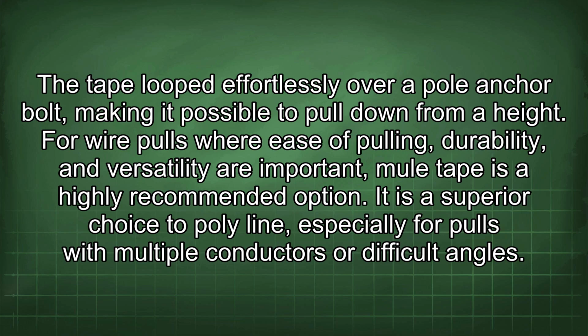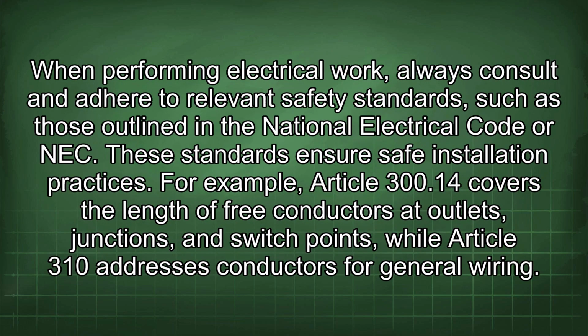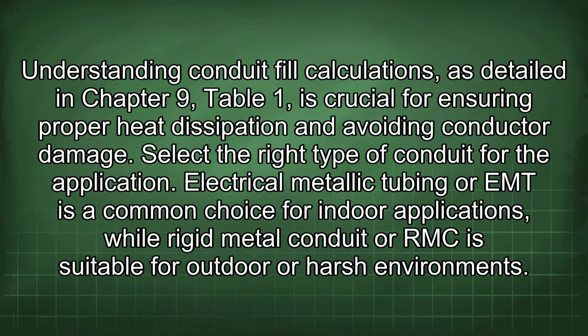For wire pulls where ease of pulling, durability, and versatility are important, Mule tape is a highly recommended option. It is a superior choice to polyline, especially for pulls with multiple conductors or difficult angles. When performing electrical work, always consult and adhere to relevant safety standards such as those outlined in the National Electrical Code, or NEC. These standards ensure safe installation practices. For example, Article 300.14 covers the length of free conductors at outlets, junctions, and switch points, while Article 310 addresses conductors for general wiring. Understanding conduit fill calculations, as detailed in Chapter 9, Table 1, is crucial for ensuring proper heat dissipation and avoiding conductor damage.